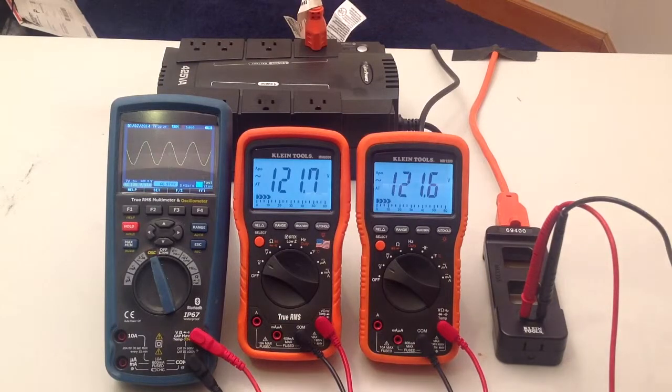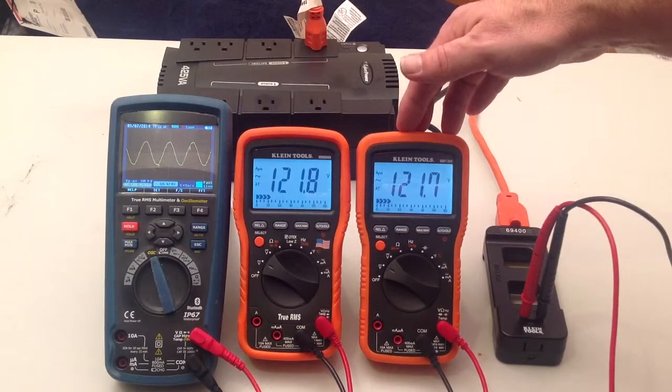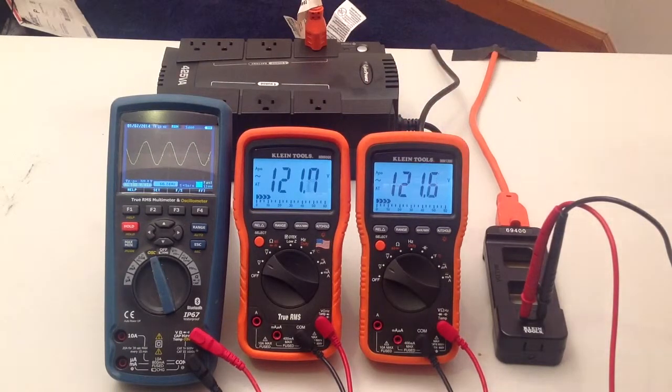When you have a perfect sine wave like this, an RMS meter and a true RMS meter show the same voltage. Here I have an MM6000 true RMS meter and an MM1300 RMS meter. They are measuring essentially the same voltage, within a tenth of a volt. Sometimes they are measuring the same voltage.